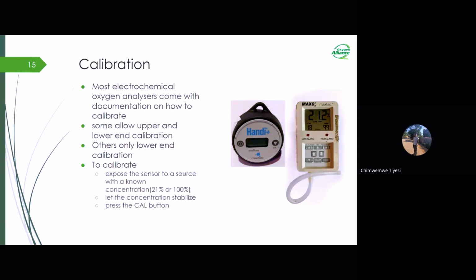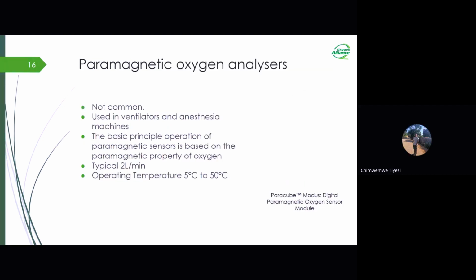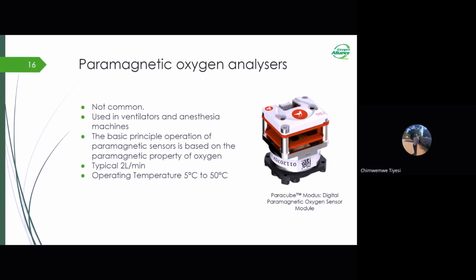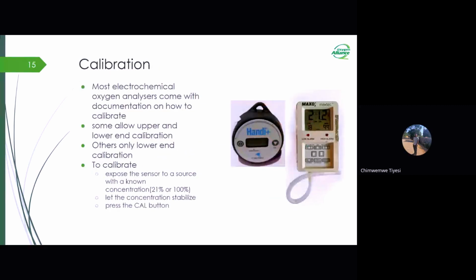So for the one where you can calibrate the lower and upper end, and also have buttons that allow adjusting the concentration, you can first start by exposing the sensor to a source of oxygen with a known concentration. It can either be room air, which is at 21%, or 100% oxygen from oxygen cylinders or whatever source is outputting 100% oxygen. After exposing the sensor, you allow the readings on the sensor or analyzer to stabilize. After they have stabilized, you can hit the calibration button.